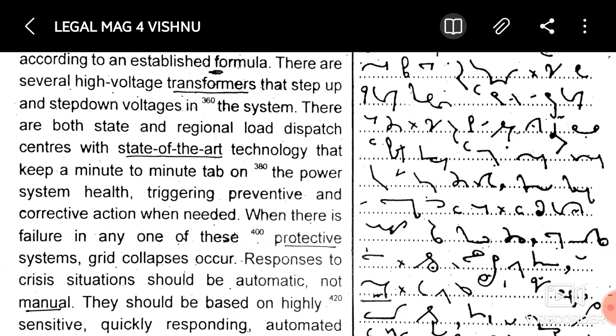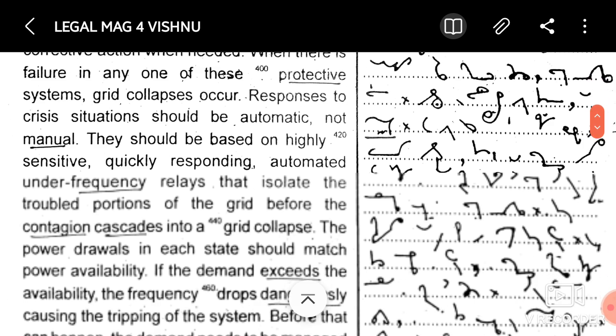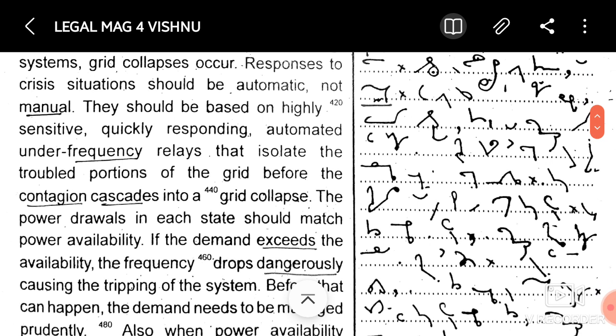Responses to crisis situations should be automatic, not manual. They should be based on highly sensitive, quickly responding automatic under-frequency relays that isolate the troubled portions of the grid before the contagion cascades into a grid collapse.